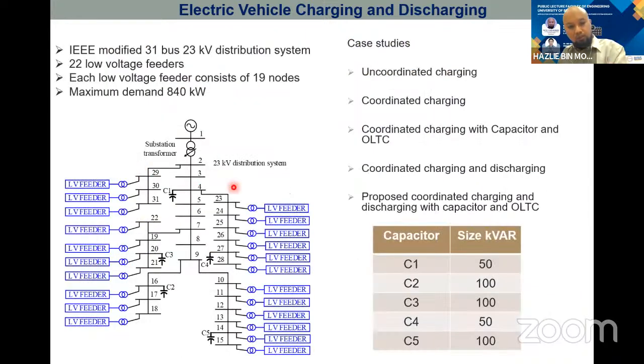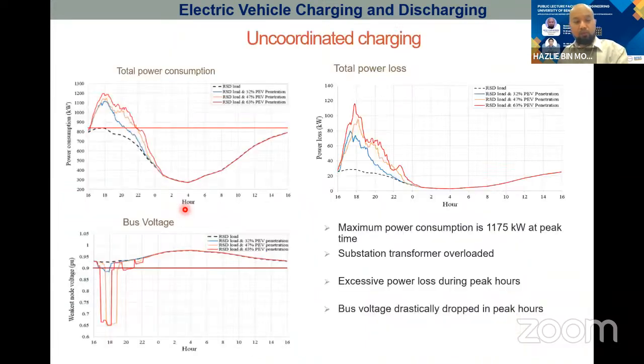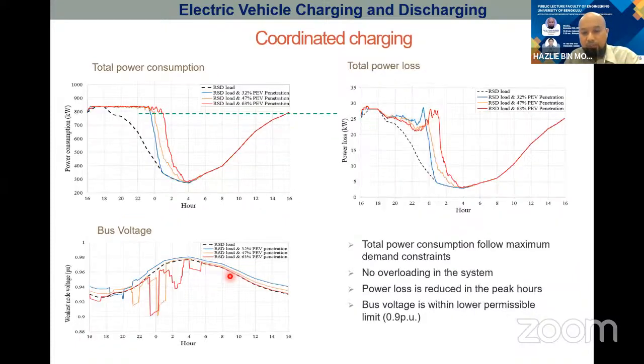Imagine this is the transformer. Once everybody starts to charge the car, the transformer becomes overloaded, and the line also becomes overloaded. So it creates an issue in terms of security of the system. Without coordination, you can see the voltage here drops to 0.65 per unit.